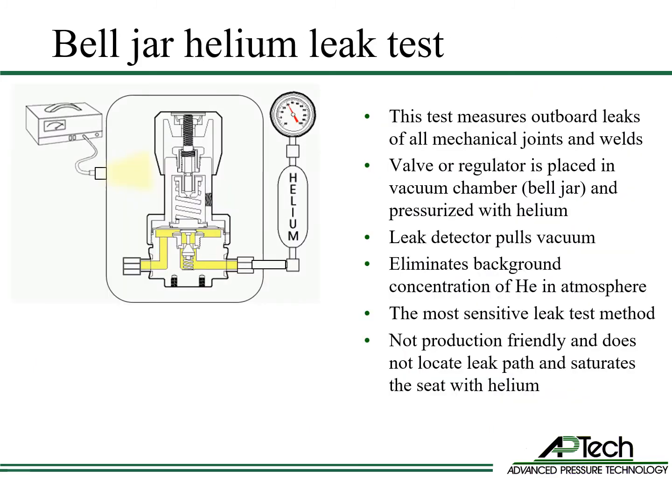The bell jar helium leak test measures outboard leaks of all mechanical seals and welds. The regulator is placed in a vacuum chamber — the bell jar — and the regulator is pressurized with helium. The leak detector pulls vacuum in the bell jar. This eliminates the background concentration of helium in atmosphere, allowing much greater test sensitivity. However, this method is not production friendly as it takes time to set up and perform the test. This method also does not allow the location of the outboard leak path to be identified, and it saturates the seat with helium.